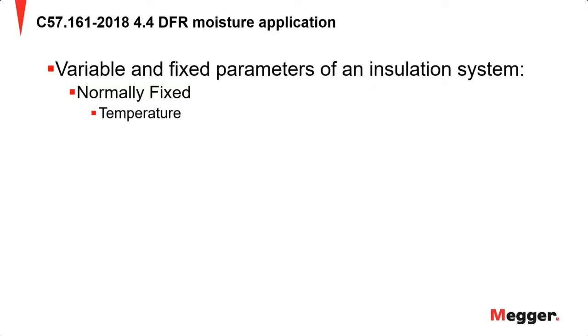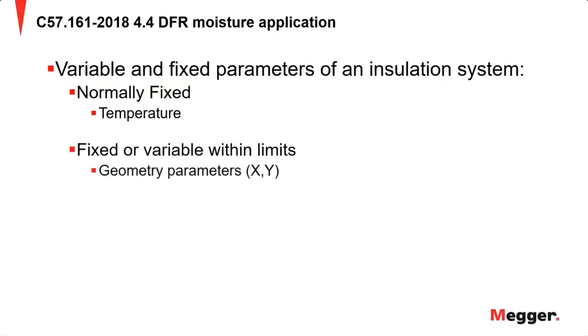And what's normally fixed or variable within limits is going to be the paper and the oil inside the OIP. Those geometry parameters, normally those are pretty standard for sister bushings. That's not going to change. And then in addition to that, the geometrical capacitance. So if you look at the capacitance within the transformer, or the bushing, I should say, it's not going to change over time if there has been no degradation.